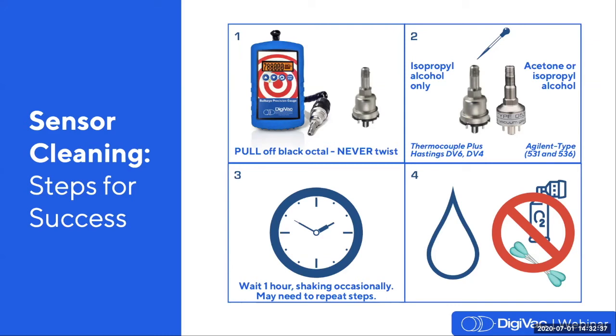Once your sensor is clean, you'll want to just sit it and let it dry in ambient air, or it can be dried under vacuum without a gauge attached. You should not use a cotton swab or compressed air to attempt to dry the interior of the sensor faster. Remember, we've got those two very delicate filaments inside, so if they're poked with a cotton swab or blasted with compressed air, they can come apart, and then the sensor will need to be replaced. So we definitely don't recommend doing that. And once you consider the sensor dry, you can plug it back into its gauge and read vacuum.